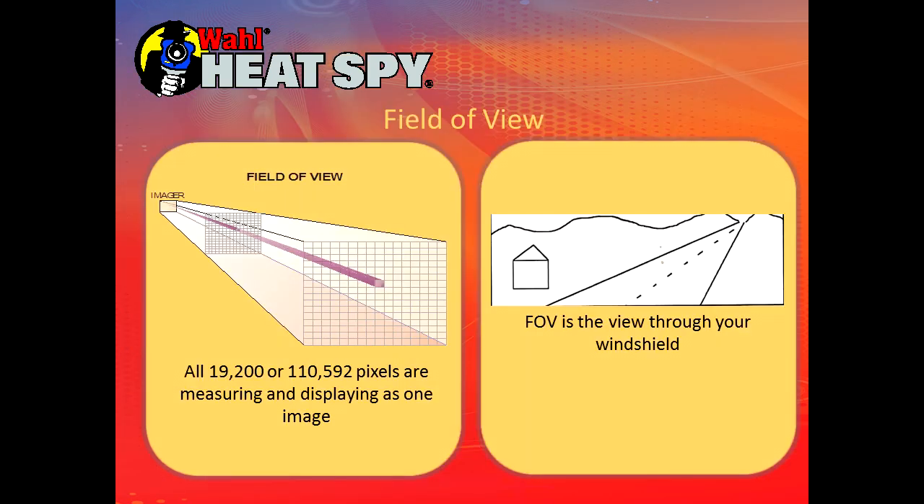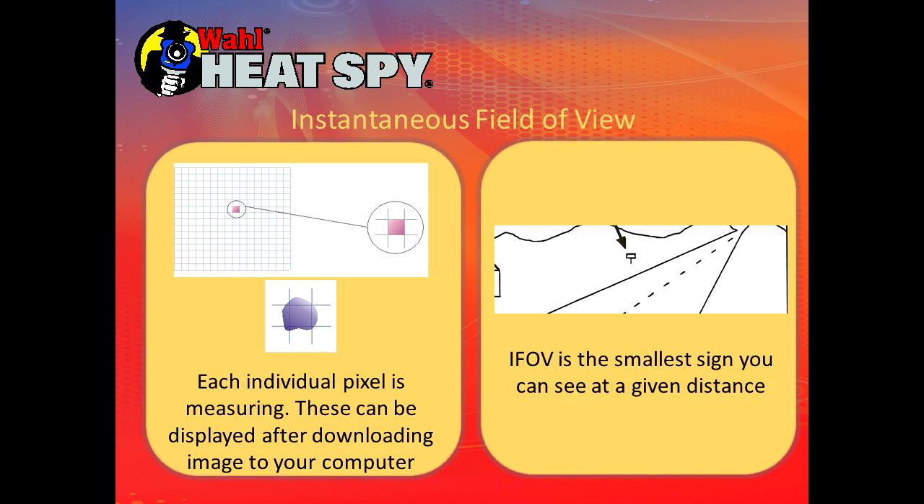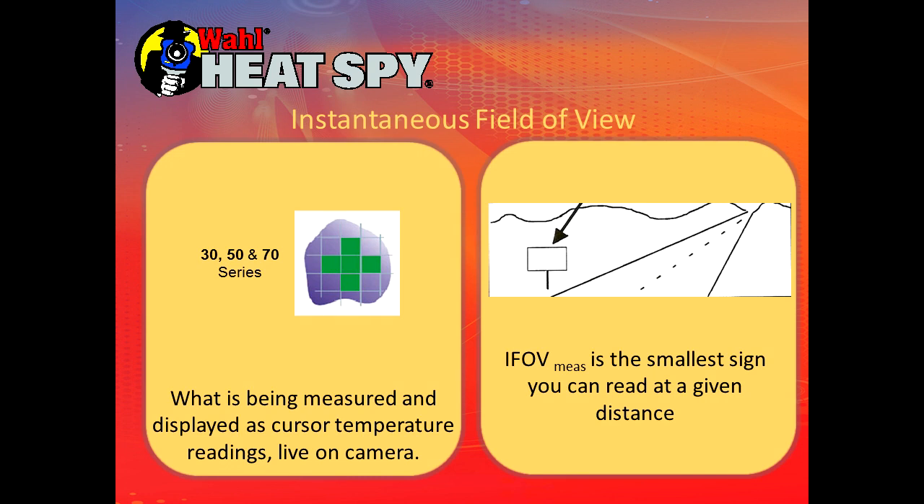The 160 by 120 imager has 19,200 pixels in the array. A 320 by 240 imager has 76,800 pixels. Our 384 by 288 has 110,592 pixels — almost 45% more pixels than a 320 by 240 — giving a much sharper image once downloaded to your computer, though you won't be able to see it on the screen. The instantaneous field of view is the smallest thing measured, visible once downloaded. The block of pixels being measured live is what the cursor shows — that's the smallest target you can see live on the camera and get a temperature on.